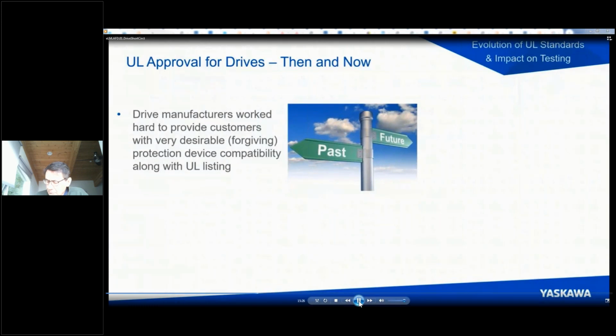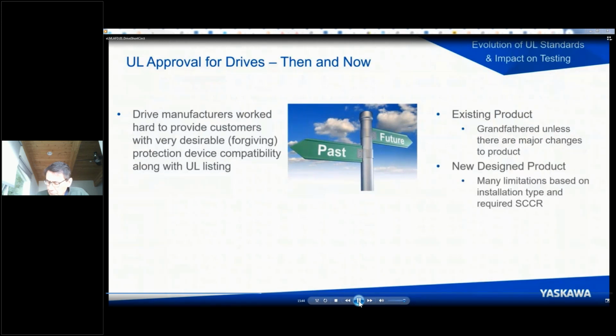provide customers with these very desirable and forgiving compatibility from these devices along with the UL listing. Now, existing product is grandfathered unless there are major changes to the product. But new product now, under the new UL testing requirements, has many limitations. This new product does, based on installation type and the required short circuit current rating that customers need.